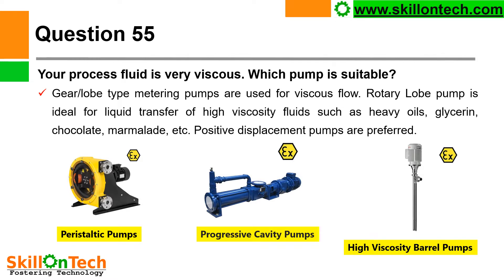Question 55: Your process fluid is very viscous — which pump is suitable? Gear and lobe-type metering pumps are used for viscous flow. Rotary lobe pumps are ideal for liquid transfer of high viscosity fluids such as heavy oils, glycerin, chocolate, marmalade, etc. Positive displacement pumps are preferred. You can see pictures of peristaltic pumps, progressive cavity pumps, and high viscosity barrel pumps.